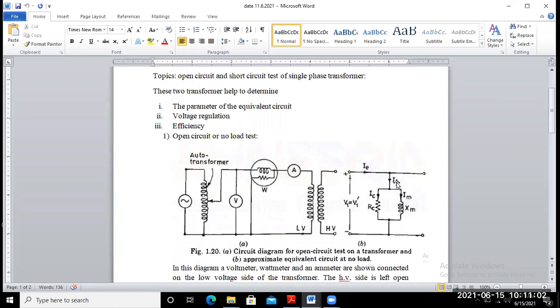At the rated voltage, we perform this test. With the help of an auto transformer, when you change the position of this variac, you are able to change the supply voltage. That supply voltage you continuously measure with one voltmeter. When the rated voltage is measured on this voltmeter, we stop the movement of the variac or auto transformer, and at this rated voltage we note down all the instrument readings: voltmeter, wattmeter and ammeter.